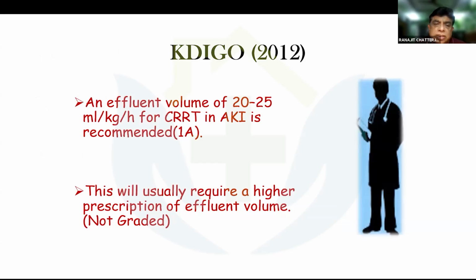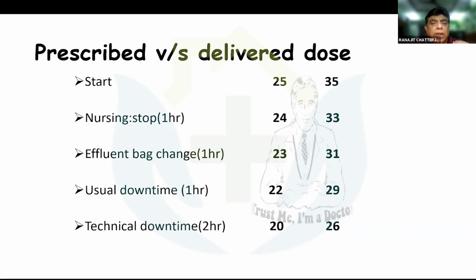So the dose that KDIGO was telling is that the effluent volume should be 20 to 25 ml per kg per hour for CRRT in AKI, but it has a lot of downtime. See, when you are starting your CRRT, if you start at 35, you may have certain stoppages, like nursing stoppages, the effluent bag change, the usual downtime. There is some technical downtime. So if you start at 35, you end at 26. If you start at 25, you end at 20. So basically, you have to prescribe more to achieve what you want. That is the meaning. So if you want to target 25, you set 35 ml per kg per hour and divide this equally among your dialysate and ultrafiltrate. That is the prescription part, which is very difficult to explain here in this short time, but I'll try to tell as much as possible.